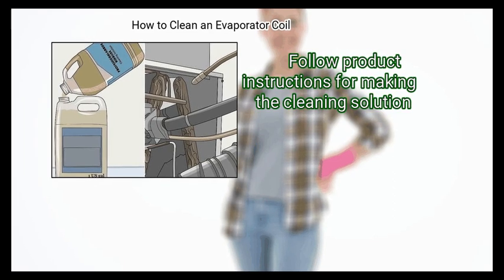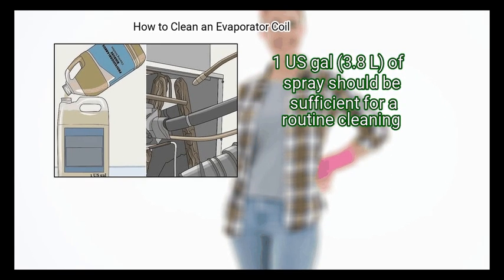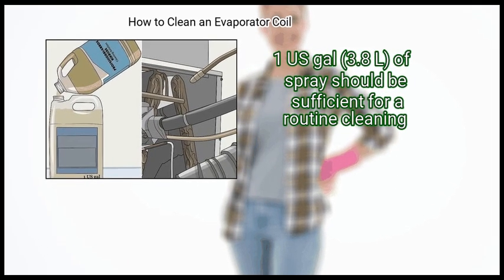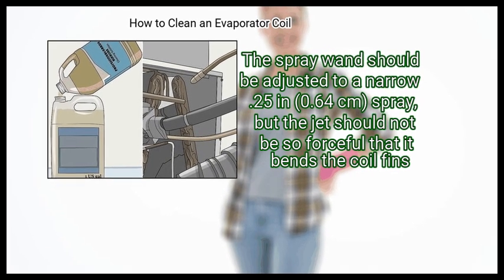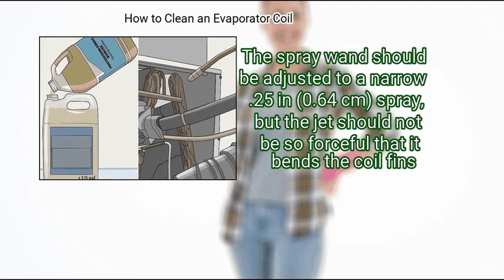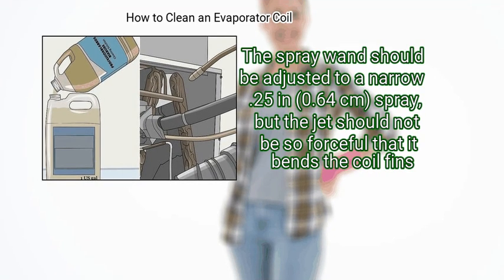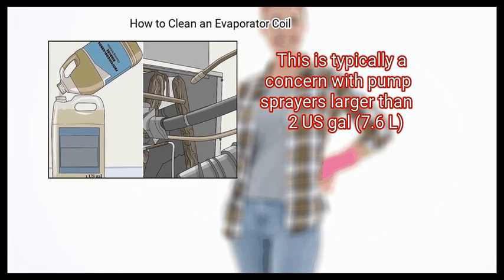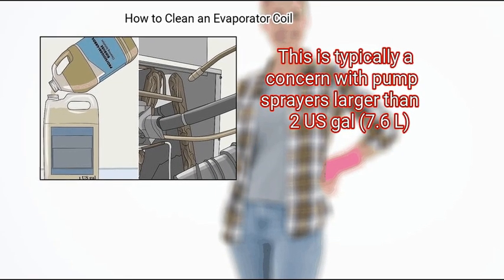Step 2. Mix the cleaning solution and spray the coils. Follow product instructions for making the cleaning solution. 1 US gal, 3.8 L, of spray should be sufficient for a routine cleaning. The spray wand should be adjusted to a narrow 0.25 in, 0.64 cm spray, but the jet should not be so forceful that it bends the coil fin. This is typically a concern with pump sprayers larger than 2 US gal, 7.6 L.